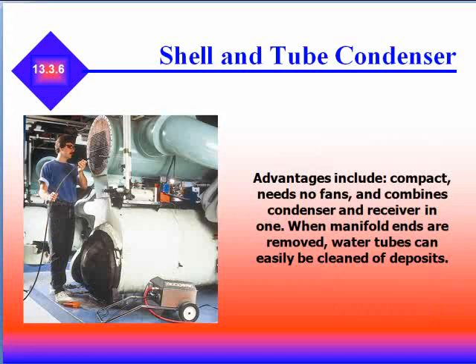Advantages of the shell and tube condenser include compact design, no fans, combines condenser and receiver in one unit, and when manifold headers are removed, the water tubes can be easily cleaned of deposits.